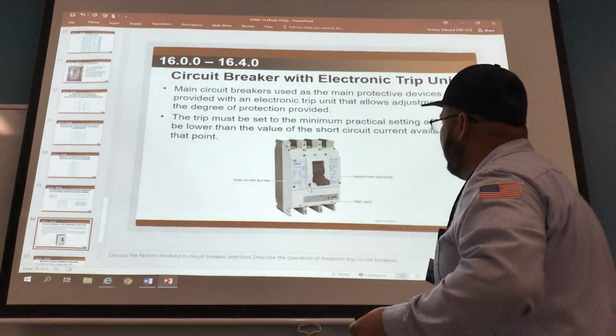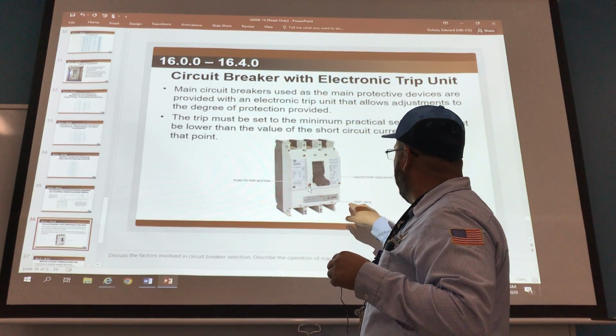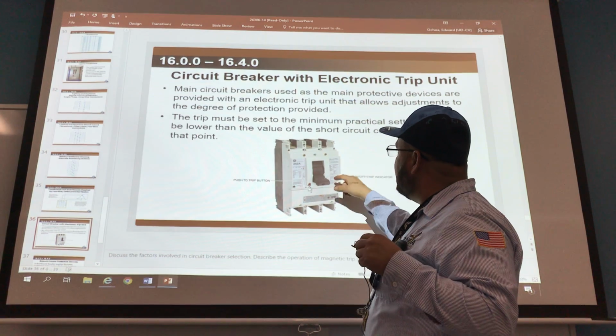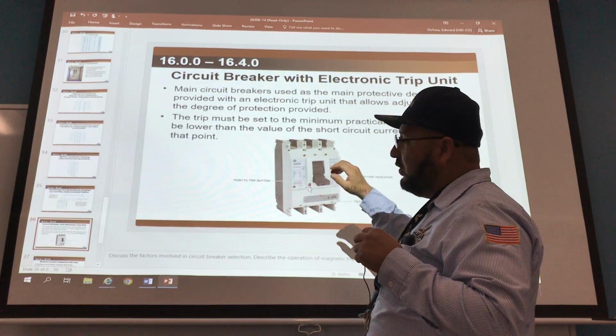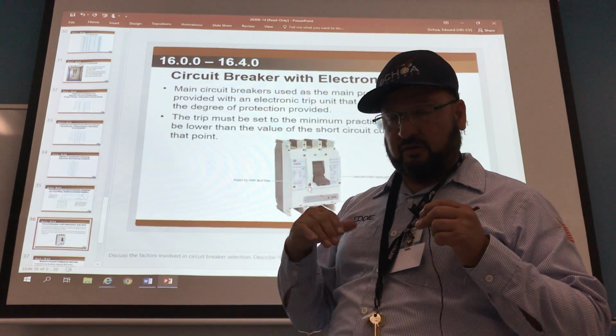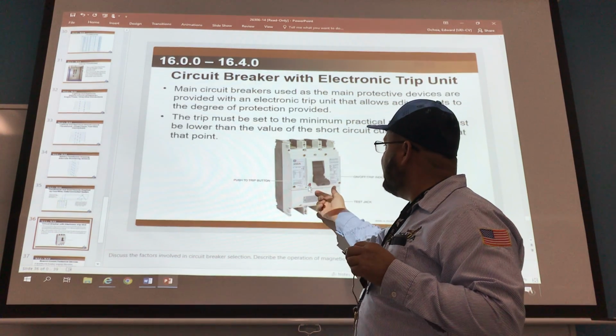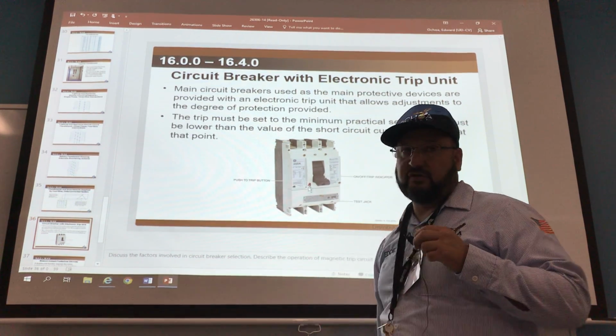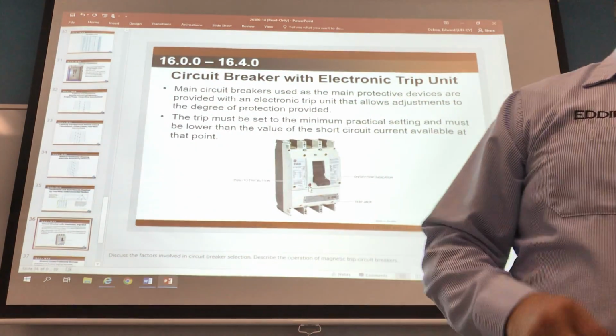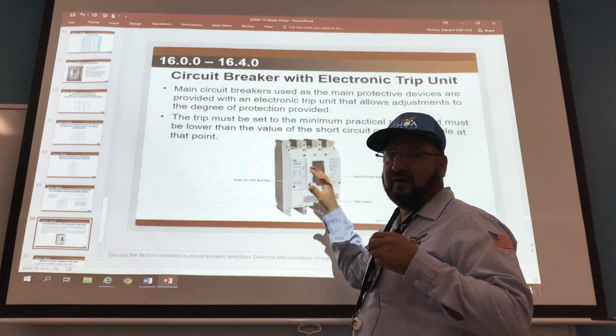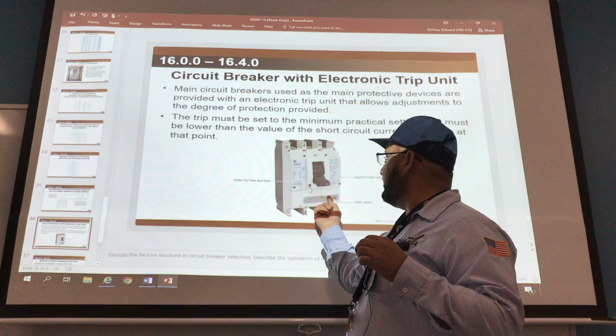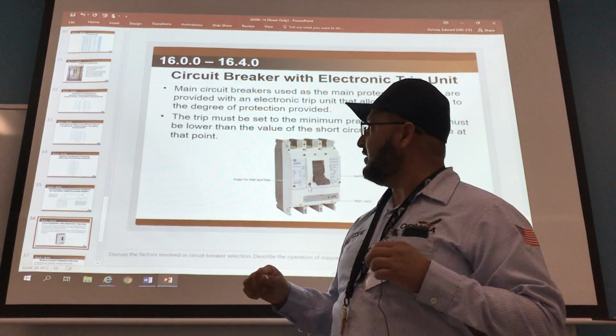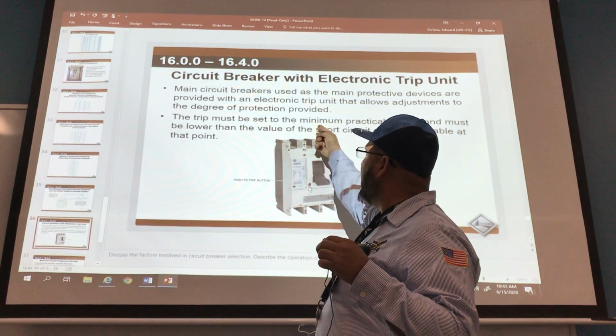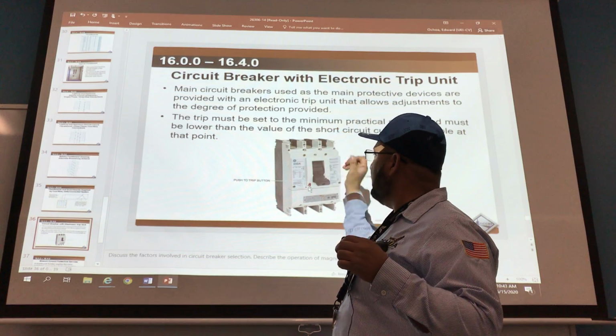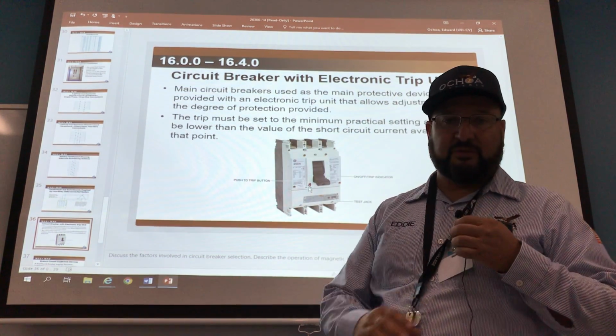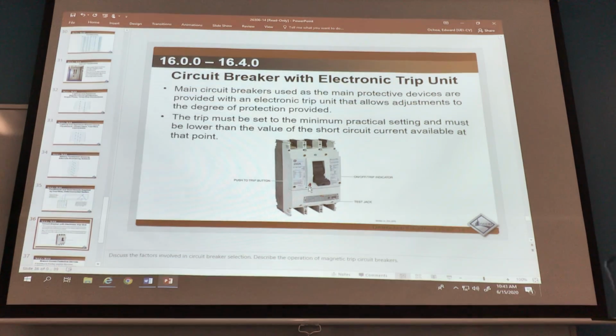Okay, this breaker right here: push to trip, on, off, test jack. Sometimes these breakers have functions at the bottom where you can actually dial in how many amps it will trip at, raise it or lower it. I've seen them where, when they sent them out, the dials were all the way to the left, down to like 0 or 1, and every time you put a load on it, it would trip constantly, and everything was fine. A lot of journeymen don't realize that this breaker has a function, and they rack their brains because every time they turn on the breaker, it stays on for 10 minutes and trips at a lower amperage. That's why you need a clamp-on amp meter. You clamp onto it, test it out, see where you're at. If it's tripping at lower amps, then most likely your adjustable breaker is not adjusted properly.